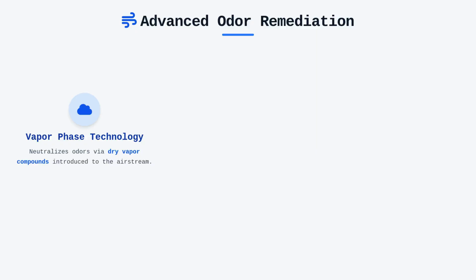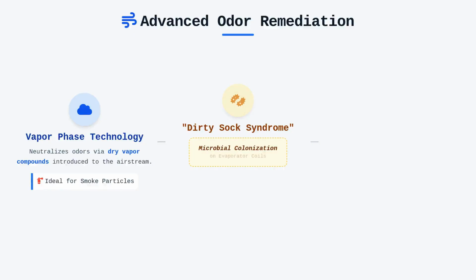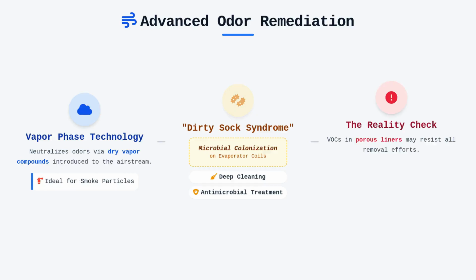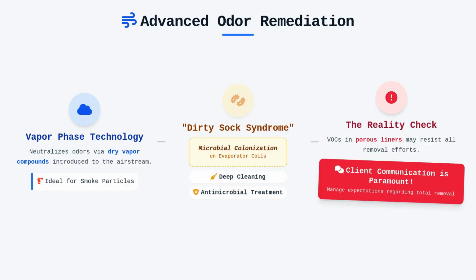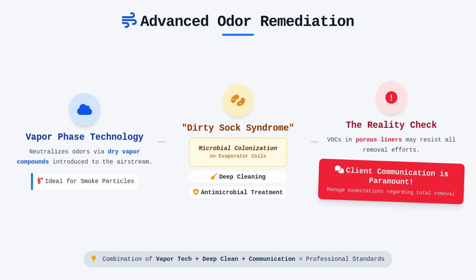Vapor phase technology offers another layer of treatment, often by introducing dry vapor compounds into the airstream to neutralize odors through contact. This is particularly useful in fire restoration projects where smoke particles have permeated porous materials throughout the ductwork. If you are dealing with dirty sock syndrome in heat pumps, which is often tied to microbial colonization of the evaporator coil, the approach must involve both deep cleaning and potential application of antimicrobial surface treatments. The persistent nature of volatile organic compounds within porous duct liners means that sometimes, regardless of your effort, source removal is insufficient. In such cases, informed communication with the client is paramount because they must understand that total removal of deep-seated odors in significantly contaminated systems is not always a realistic guarantee.